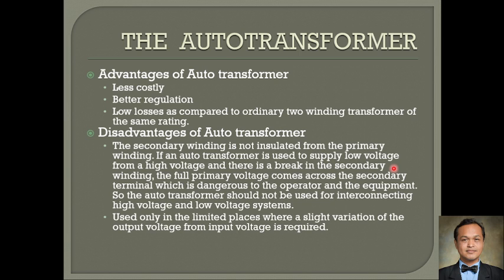Now, another disadvantage of the auto transformer is that it is used only in limited places where a slight variation of the output voltage from the input voltage is required. It doesn't need a big difference, such as if we're going to put the auto transformer in a 138 kV to 13.8 kV. So auto transformer is not for that kind of application because it has a bigger difference between the low voltage side and the high voltage side.